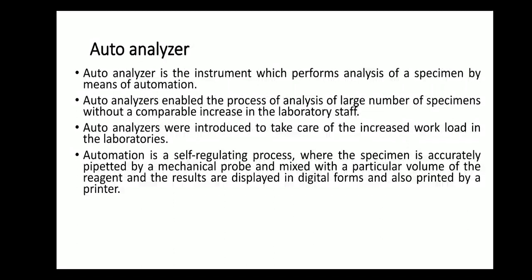Okay, so autoanalyzer, it was introduced to take care of increased workload primarily. Then this analyzes large number of specimen without comparable increase in laboratory staff. That is the advantage of this autoanalyzer. This works on automation. Okay, and this automation is a self-regulating process where the specimen which you have to analyze is pipetted out accurately. It is mixed with a particular volume of reagent and the results are displayed in the digital form. The displayed results can be taken print also.